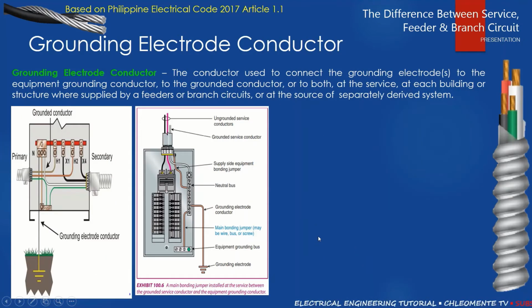Grounding electrode conductor naman, so sabi ni PEC, the conductor used to connect the grounding electrode to the equipment grounding conductor, to the grounded conductor, or both at the service, and each building or structure were supplied with a feeder or branch circuit, or at the source of a separately derived system. So ano yung grounding electrode conductor? Yan tinatawag na conductor in between sa ating grounding electrode at saka yung ating main ground bus. So ito yung tinatawag na grounding electrode conductor.